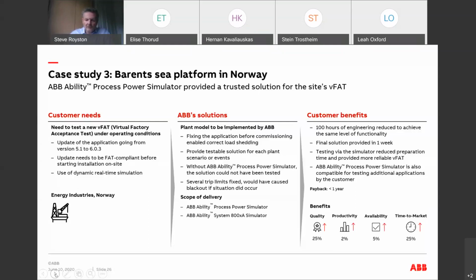So what they discovered during this testing period is that they were not able to test all the scenarios with the traditional way. They discovered that there were several trip limits which needed to be fixed, and they were actually wrongly configured in the application, which could have led to a blackout situation or a huge overload shedding, so to say, shedding too much load under such a condition, causing a process stop. So this was corrected.